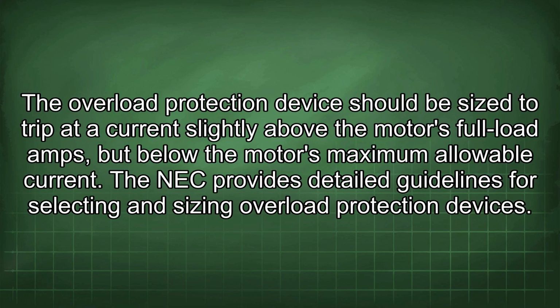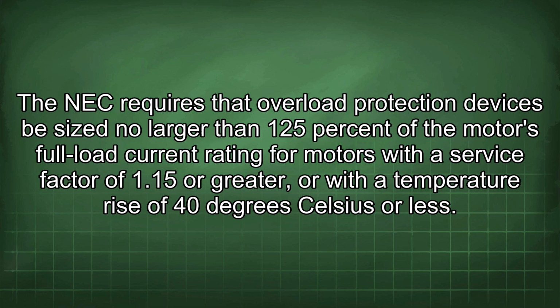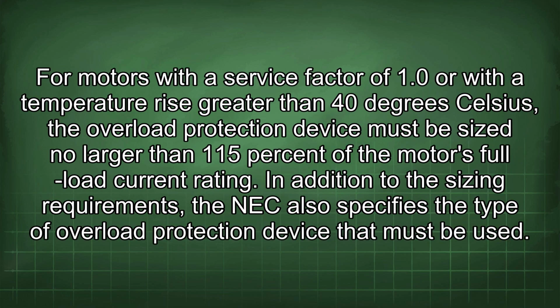The overload protection device should be sized to trip at a current slightly above the motor's full load amps, but below the motor's maximum allowable current. The NEC provides detailed guidelines for selecting and sizing overload protection devices. The NEC requires that overload protection devices be sized no larger than 125% of the motor's full load current rating for motors with a service factor of 1.15 or greater, or with a temperature rise of 40 degrees Celsius or less. For motors with a service factor of 1.0 or with a temperature rise greater than 40 degrees Celsius, the overload protection device must be sized no larger than 115% of the motor's full load current rating.